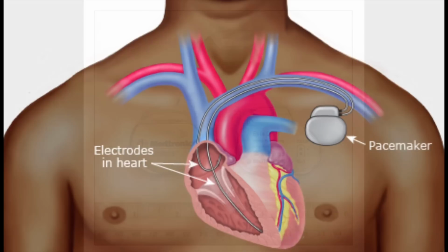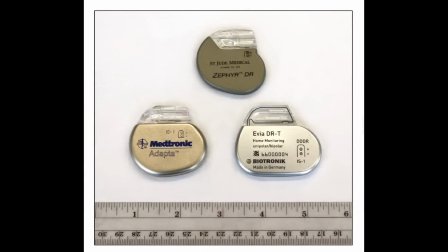An electrical impulse is transmitted to the heart muscle when needed, and the lead is also able to sense the heart's intrinsic electrical activity. A variety of types of pacemakers and modes of pacing have been developed to restore or sustain a regular heartbeat in different ways. All contemporary pacemakers sense the intrinsic activity and stimulate the heart only when the intrinsic heart rate falls below the programmed pacing rate. Essentially all contemporary pacemakers also incorporate rate-responsive capability. This depends on a sensor incorporated into the pacemaker that can sense activity or respiratory rate and can alter the heart rate based on the perceived physiologic need.